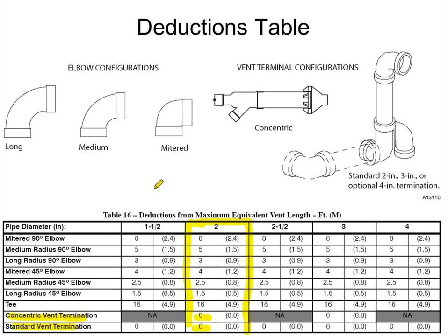And then depending on what type of elbows I use, I get bigger or smaller penalties. 90-degree elbows, if I can have a long radius, medium, or a mitered radius, it's going to have a different effect on there. So let's just say I have a medium radius, 90-degree elbows. Those are worth 5 feet. Let's say that I have 5 of them for some reason. So that's 25 feet of penalty. So now instead of 130 feet, I can run my venting pipe 105 feet. So you can see kind of how that works there.